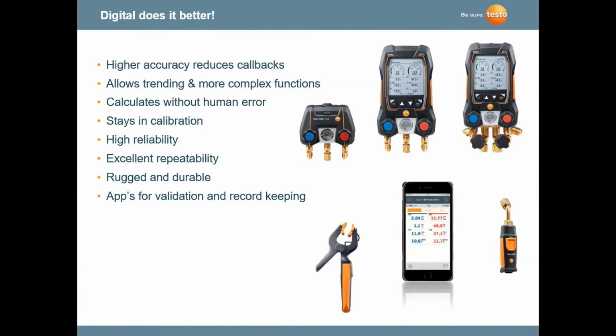Like I said, they stay in calibration. The temperature sensors do not need to be calibrated. Pressure sensors can be zeroed at any time in the atmospheric pressure, just by hitting a key on the display on the panel itself. The nice thing too about these is their excellent repeatability.